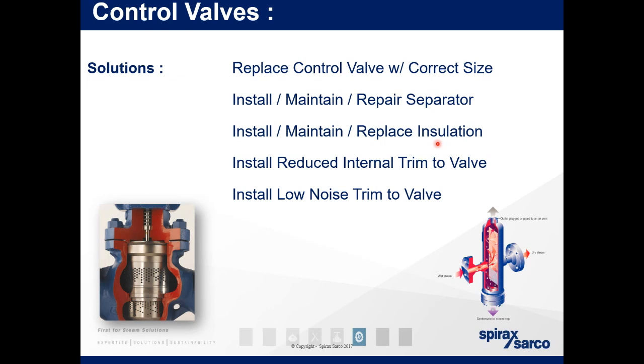Install reduced internal trim to the valve. So we want to speed it up to dry the steam out. So sizing the valve correctly again. And install low noise trims to valves. So that will reduce the noise, reduce the vibration, reduce the wear and the erosion.